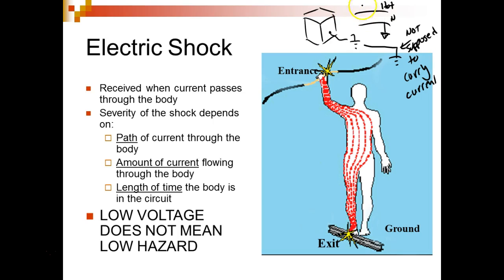So what happens if this hot lead, which has got a little bit of insulation on it, comes in contact with this? Instead of my whole refrigerator becoming electrically hot, it pops a breaker because now there's current flow in the ground. The ground's not supposed to have current flow in it, right? So it creates a short circuit.